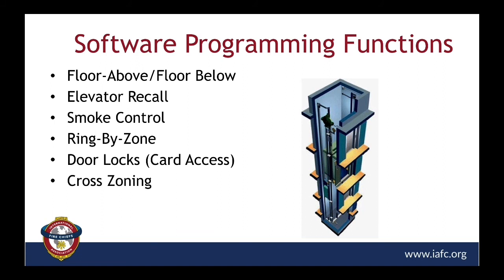Along with the fact that we're addressable, we're entering the world of a software program being required. Different levels of advancement are necessary, but the fact of the matter is, when a device goes off, the panel can be and needs to be programmed to tell it what to do. Do I sound all the horns? Do I sound only the horns on a certain floor? Do I trip the signal to the fire department? And as you can see here, do I activate elevator recall?